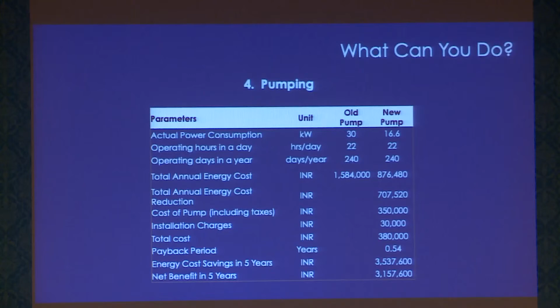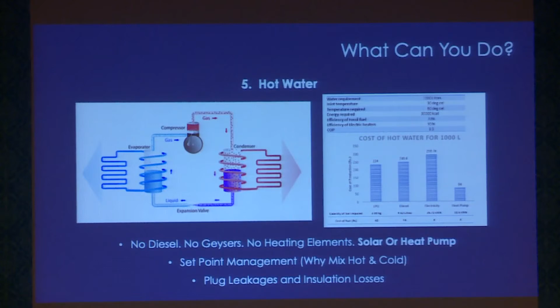So next, the hot water pump. In hospitals, hot water is a must. They might be using it for sterilizing, laundry, and a lot of other purposes. But they are following a bad practice. They are either using diesel-fired boilers or electric boilers, which consume 3 times more energy than the modern equipment, that is known as a heat pump. A heat pump only consumes 1/3 of the energy compared to the electric boilers as well as the diesel-fired boilers. It can simultaneously generate hot water as well as cold water, and hot water can be supplied to the buildings by storing it in tanks and circulating it throughout the building. And the cold water is supplied to the chiller, which can ultimately reduce the load of the chiller, and this can also impact savings on your energy bill.